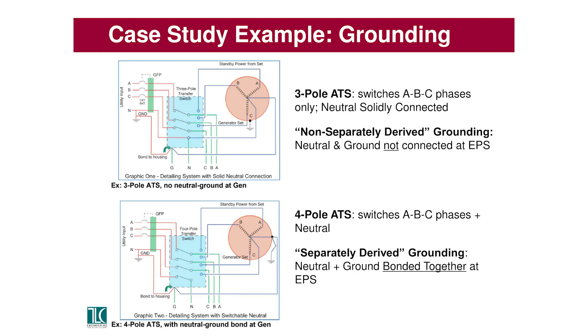It's a little technical, a little dense, and the one thing I want you to take away is that if you're near generators and have to oversee their testing or talk to the guy doing their testing, this is a thing. With non-separately derived grounding systems you need 3-pole transfer switches, and with separately derived grounding systems you need 4-pole transfer switches.